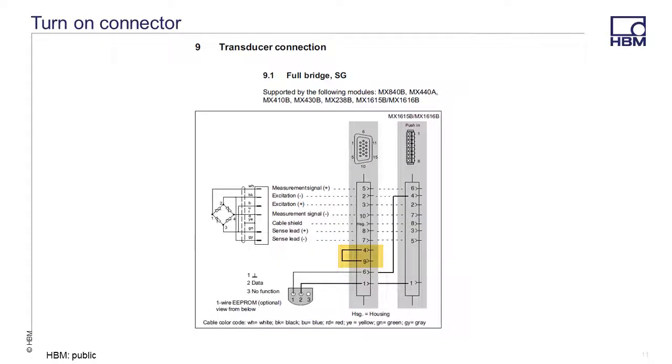Some QuantumX modules do not activate a connector until two pins are jumpered. Here is the full-bridge wiring diagram for an MX840B. Notice that pins 4 and 9 are jumpered. This jumper activates the connector. If the connection is not made, the connector will not be activated. It is not optional.